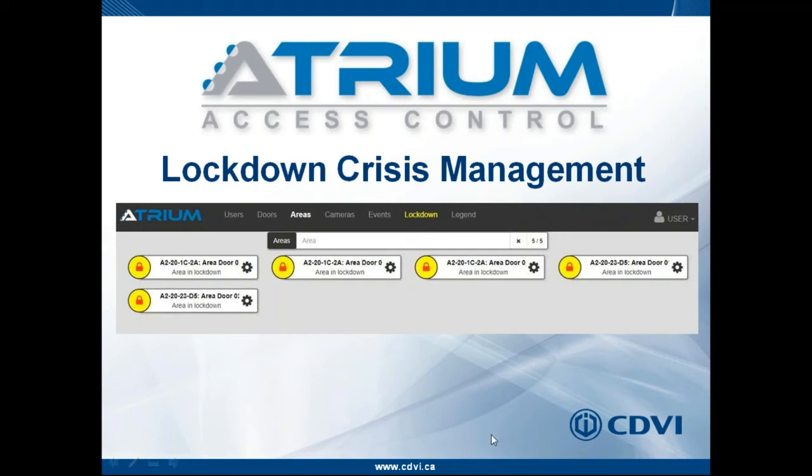So what we're looking at here is the lockdown has been initiated, has been started. The lockdown term here will blink. It's in yellow. It'll flash. The ATRIUM logo will also be flashing constantly, along with, we're in the areas menu right now, any area in the building will be indicated here. And for each area, in other words per door, you will see if the area is in lockdown or if it has been secured or not. If the area has been secured, either through the card or through the web interface, for example, the secured areas will appear at the end of the list of doors. We will always present the areas that are still in lockdown mode at the top, at the beginning of the list.